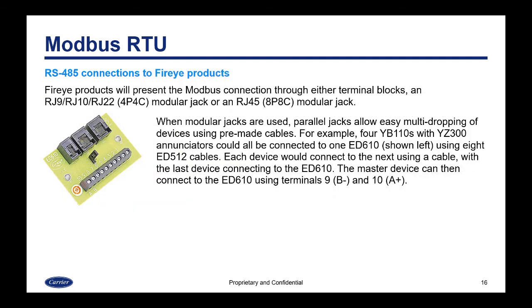Fireye products will present the Modbus connection through either terminal blocks, an RJ-9/10/22 (four-position modular jack), or an RJ-45 eight-position modular jack. When modular jacks are used, parallel jacks allow easy multi-dropping of devices using pre-made cables. Parallel jacks means two jacks beside each other on the device. For example, four YB-110s with YZ300 annunciators could all be connected to one ED610, which is the converter device shown on the left that has terminal blocks, using eight ED512 connect cables. Each device would connect to the next using a cable, and the last device would connect to the ED610. The master device can then connect to the ED610 using terminals 9 (B) and 10 (A).